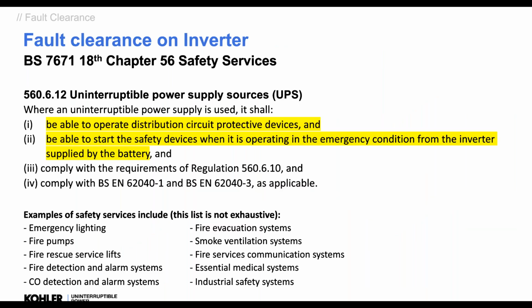All right. So if we look at BS 7671, it says where a UPS is used, it shall be able to operate the distribution circuit protective devices and start those devices in emergency condition on inverter on battery. Okay.